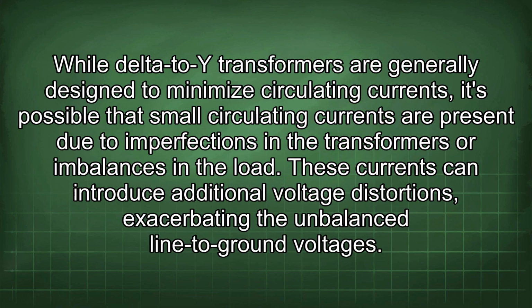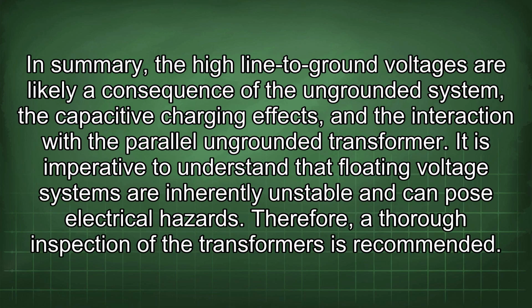While delta to Y transformers are generally designed to minimize circulating currents, it's possible that small circulating currents are present due to imperfections in the transformers or imbalances in the load. These currents can introduce additional voltage distortions, exacerbating the unbalanced line-to-ground voltages. In summary, the high line-to-ground voltages are likely a consequence of the ungrounded system, the capacitive charging effects, and the interaction with the parallel ungrounded transformer.